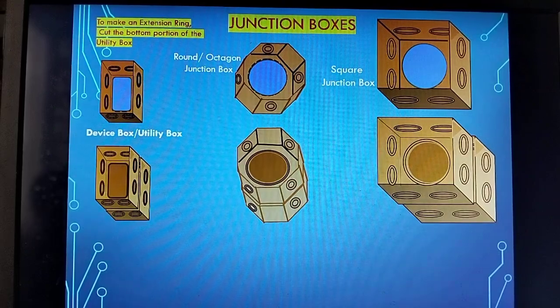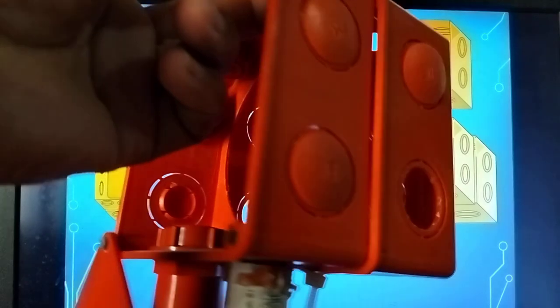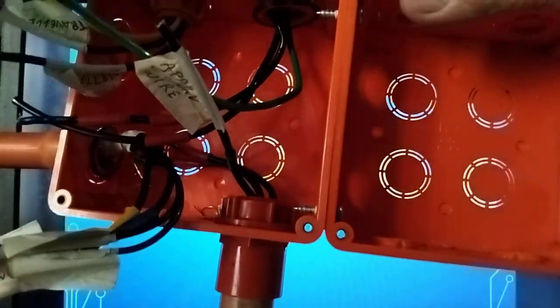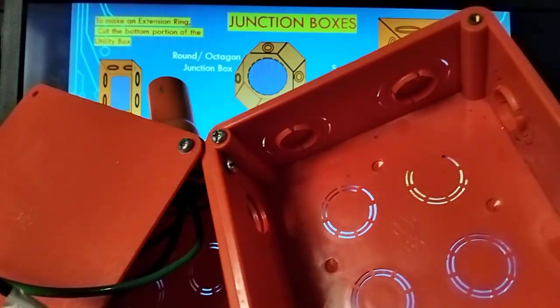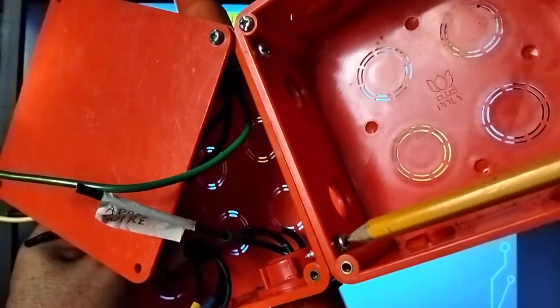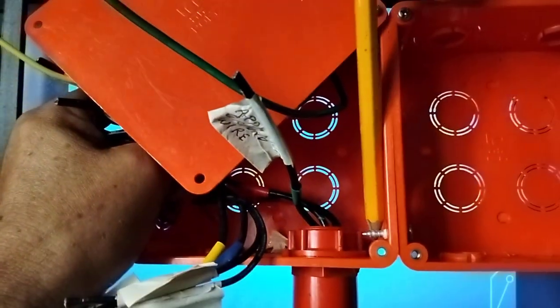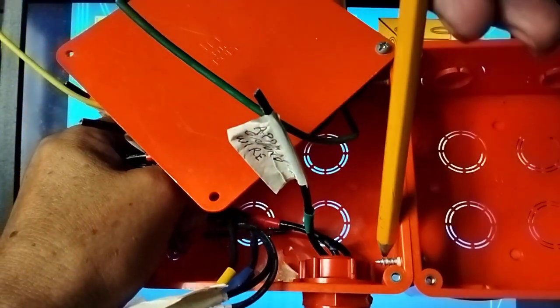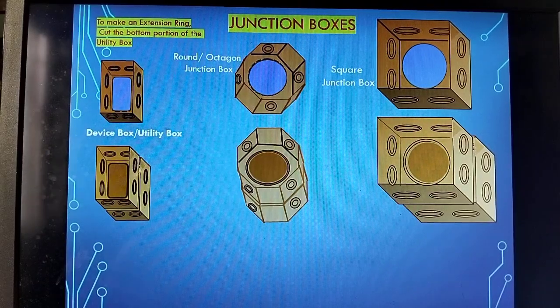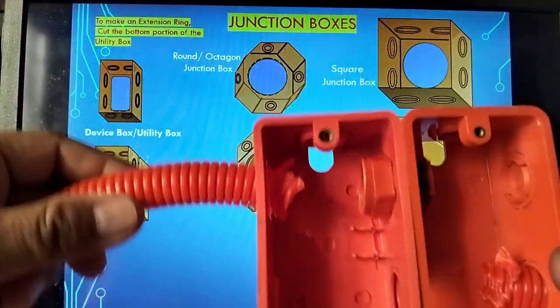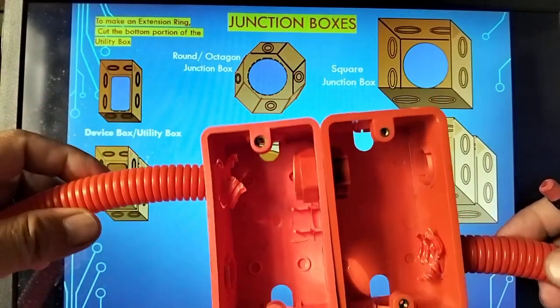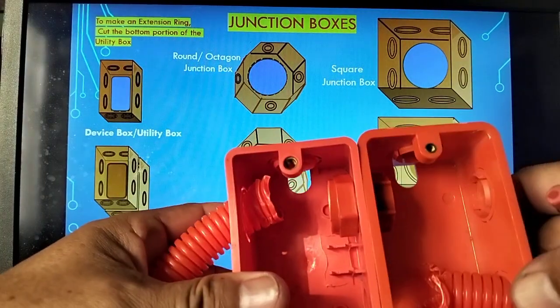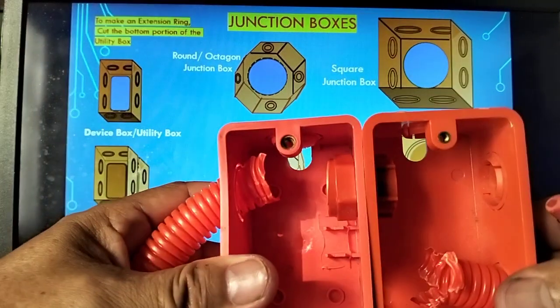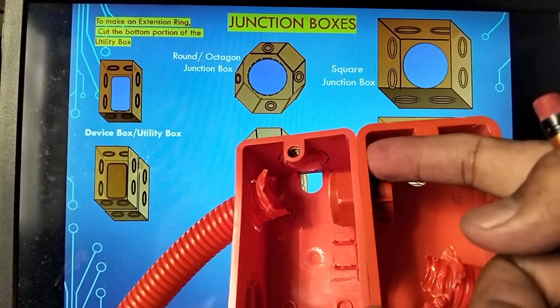Let's say on this junction box or a square box, you don't have one also, same thing, you do like this, side by side connected using the screw. See, this is a screw. Make sure you cut the excess so it will not cause injury. You just cut this one also. Same thing with the utility box or device box. Just connect using the pipe connector or bushing. Okay, this one is a lock nut. If you don't have a lock nut like this, then you use the screw or bolt.